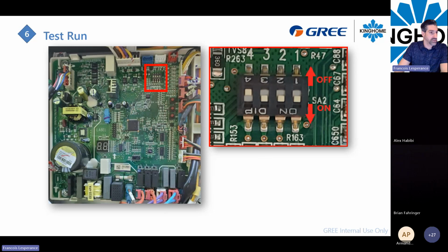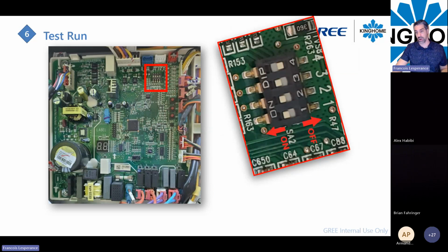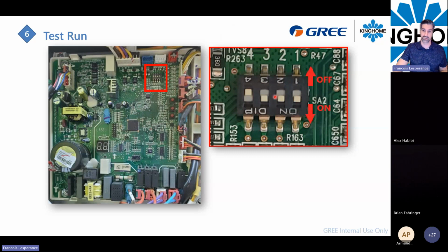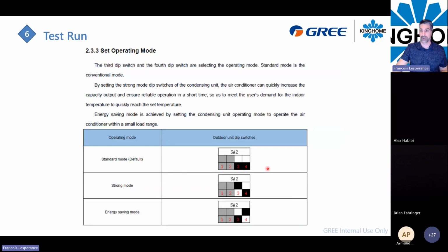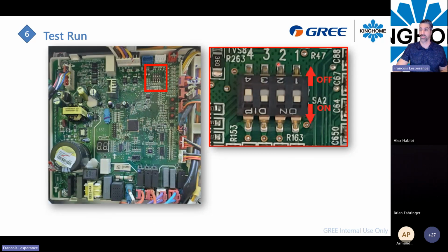I'll just go back to my slide right here. In that particular unit, it will be corrected with the new refrigerant, but right now for the R410A refrigerant system, the dip switches are upside down. You will have to figure it out from the manual. In the manual you have 1, 2, 3, 4, but in the field it's 4, 3, 2, 1, and the off position is up and the on position is down.